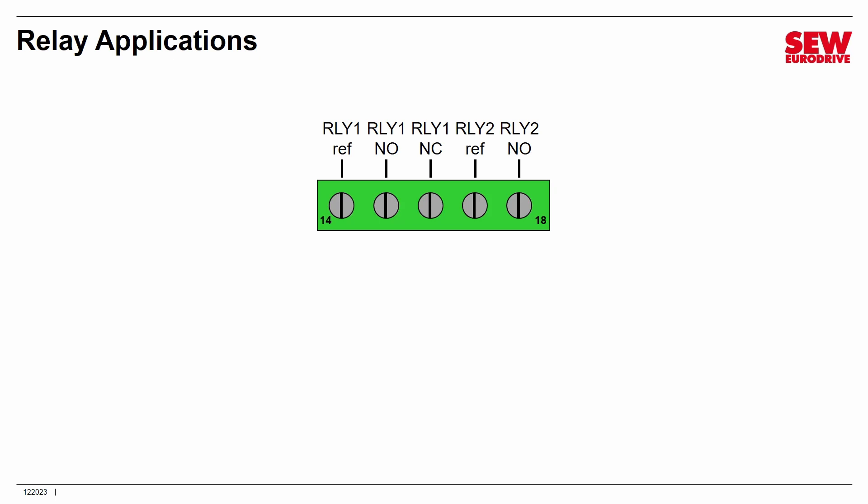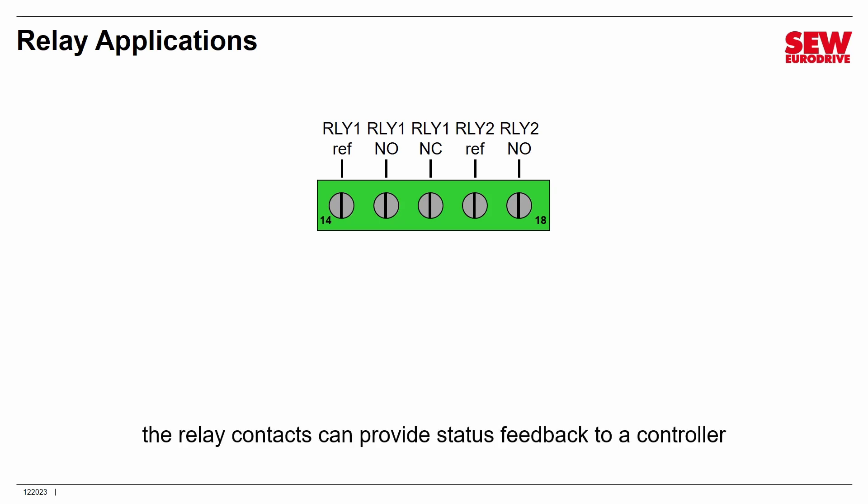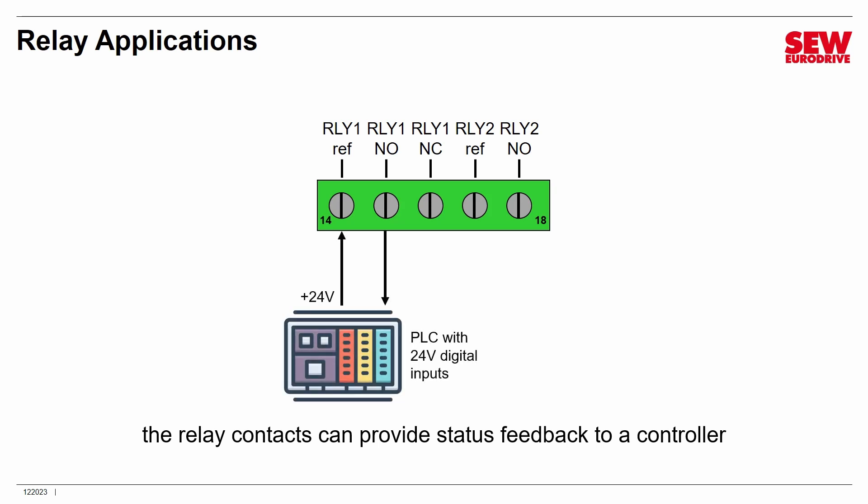There are many possible applications for the VFD relays. They can provide status feedback to a controller such as a PLC operating the VFD in terminal control mode. For example, connect the PLC's 24-volt supply to the relay reference contact, then connect the normally open or normally closed contact to one of the PLC's 24-volt digital inputs. You can then configure the relay within the VFD to tell the PLC if the VFD is healthy, running, faulted, or operating at a certain speed.